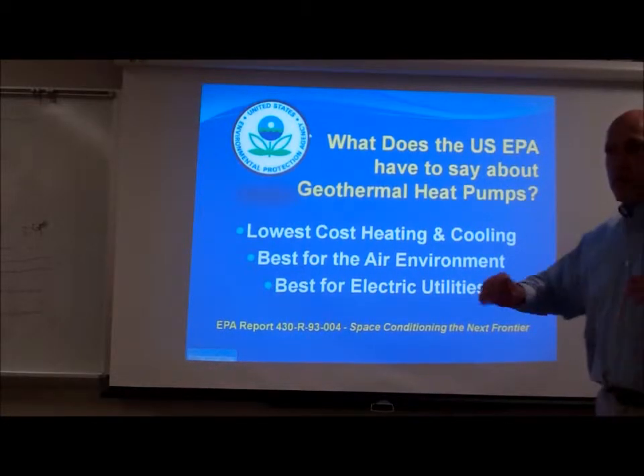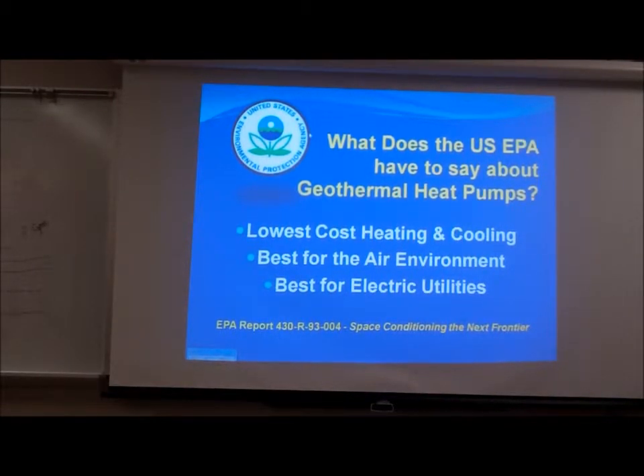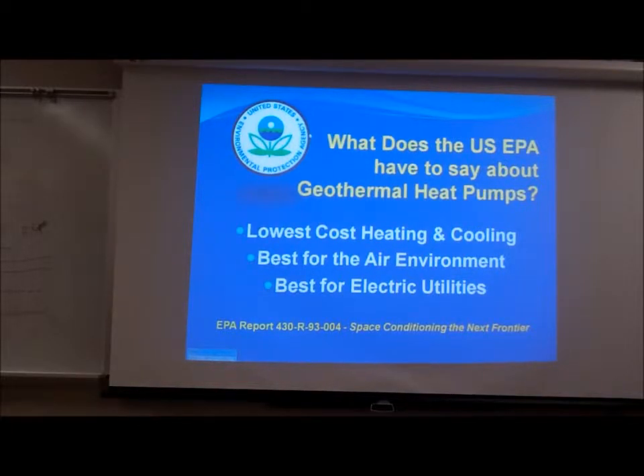When I use a geothermal heat pump, on the coldest winter day I'm losing BTUs faster than ever out of the envelope, and on the hottest summer day I'm gaining BTUs faster than ever. But the heat exchange by which I affect that envelope remains constant because the heat exchange in a geothermal heat pump relies on the 50-degree temperature that is the case all day, every day, year-round. So I'm going to run longer hours on peak days, but my heat exchange is not fighting dramatically high or low outdoor air temperatures.